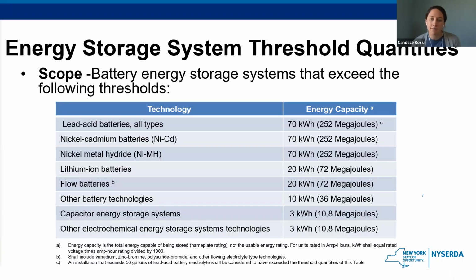All right, so to kick off this section, we're starting with the scope of the section of the IFC, which is relevant for all battery energy storage systems having capacities that exceed the value shown in this table. So any lithium ion battery system exceeding 20 kWh, so kilowatt hours, must comply with this section. If the system is in a group R3 or R4 occupancies, they will comply with a different section of this code. But this is just giving you an idea. So anything that is over these capacity thresholds will have to meet these codes.